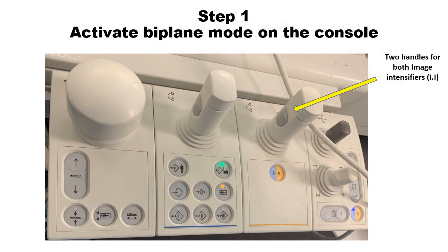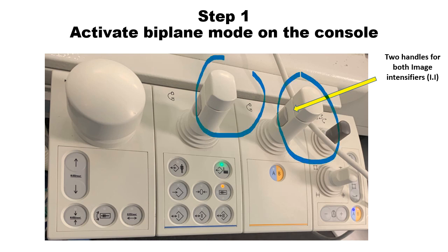So, how do we do it? Step one is to activate the biplane mode in the console and then bring the radiation sources and image intensifiers close to the patient. As you see here, there are two handles, and each of them controls one of the image intensifiers.